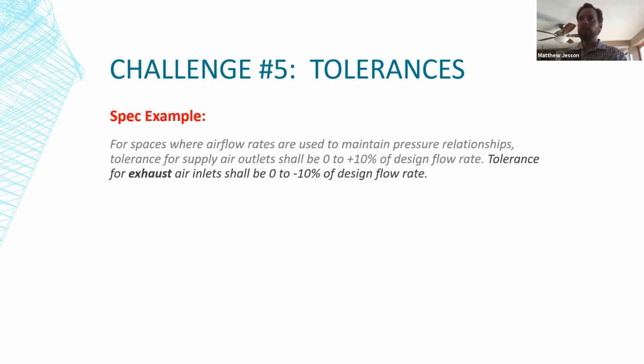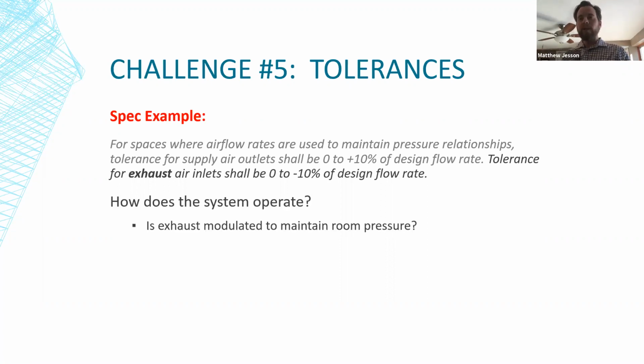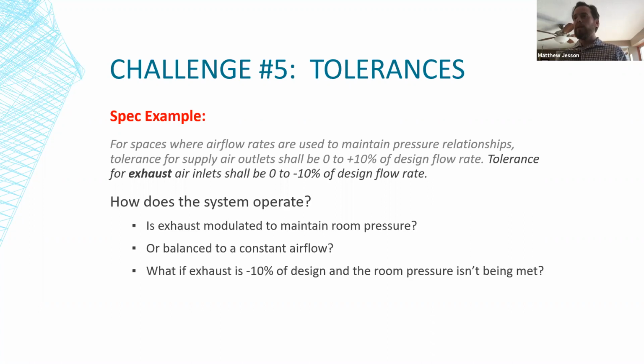Another example, and this is really just a continuation of the previous one, is, again, we're talking about rooms that require pressure relationships. It might say that your supply air is 0 to plus 10% and your exhaust air is 0 to minus 10%. So you can err on the high side on supply, but err on the low side for exhaust. Well, what we have to consider on this one is, how does this system operate where you've got room pressure control? Is the exhaust modulated to maintain room pressure, or is it balanced to a constant airflow? And if it's minus 10% of design and the room pressure isn't being met, what do you do?